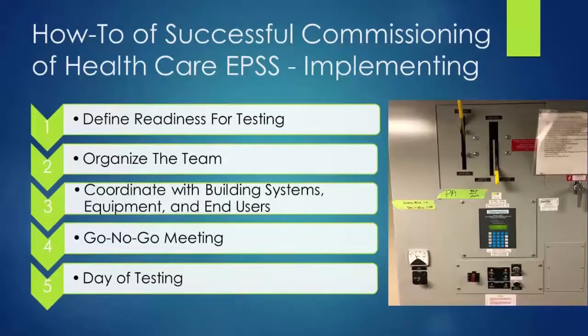If it's a brand new facility, there's a little more leeway — you can say, okay, we'll come back. But the understanding with the emergency power supply system test is that once you test it, there are no more programming changes, because you're testing the actual program. If they come in and change the program, you now potentially have a program that hasn't been proven. So ideally, everything is done before you test, and you test the finished product.